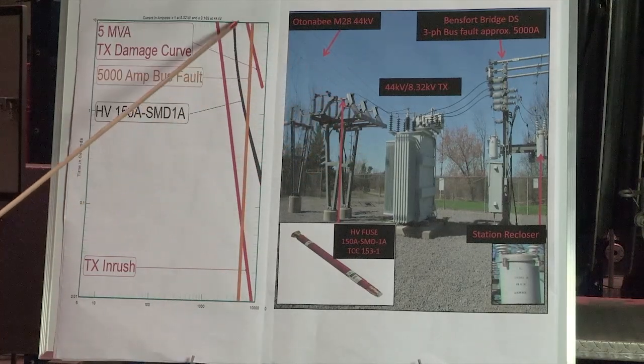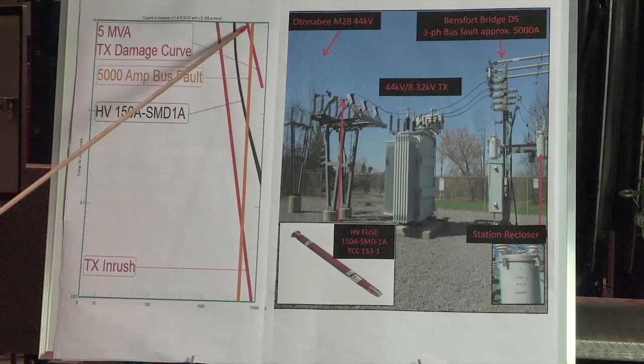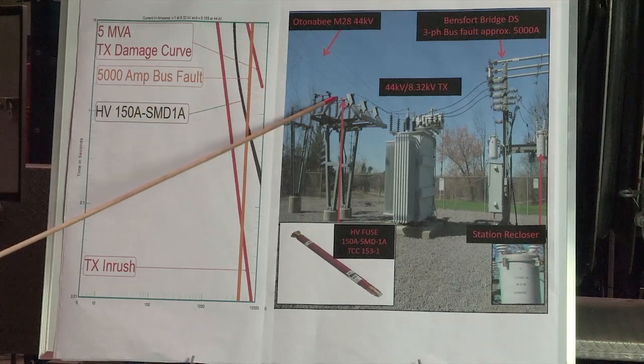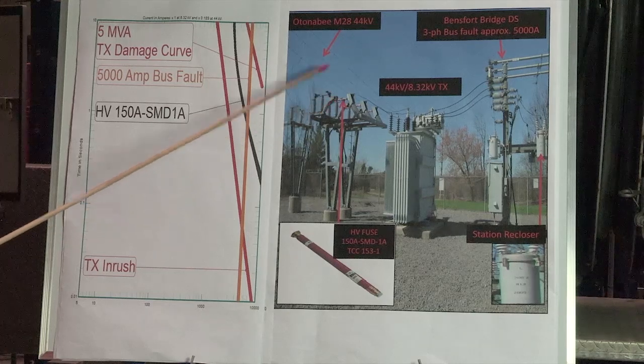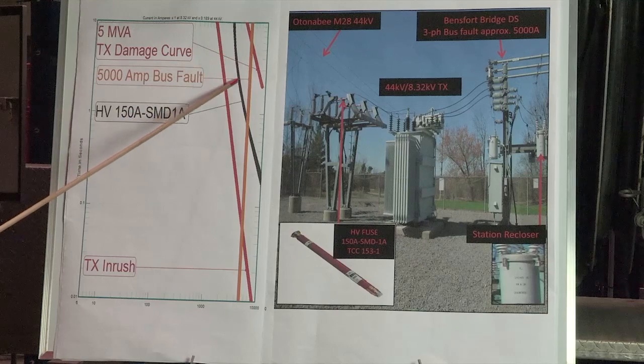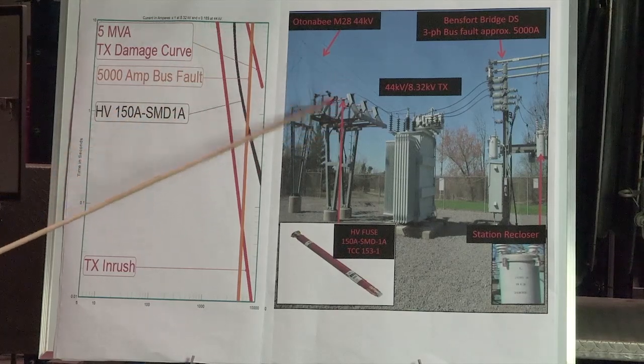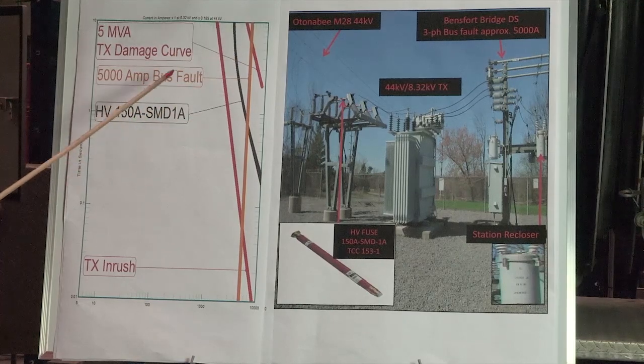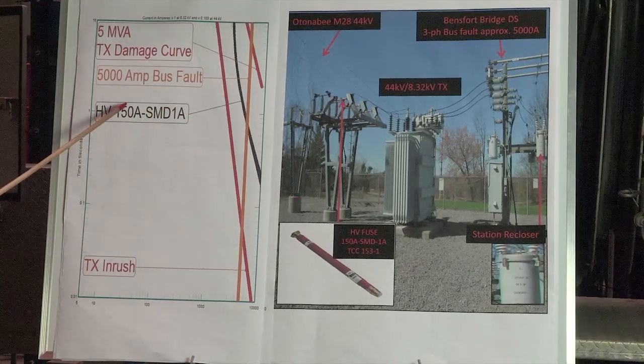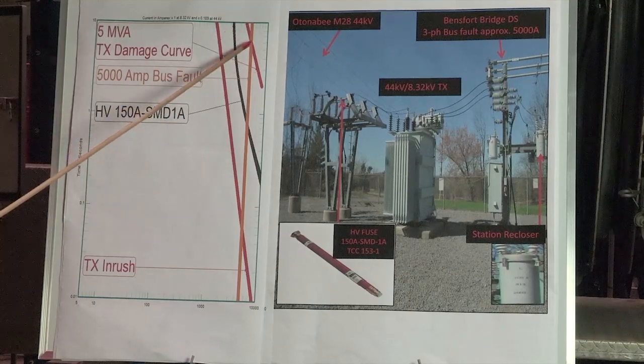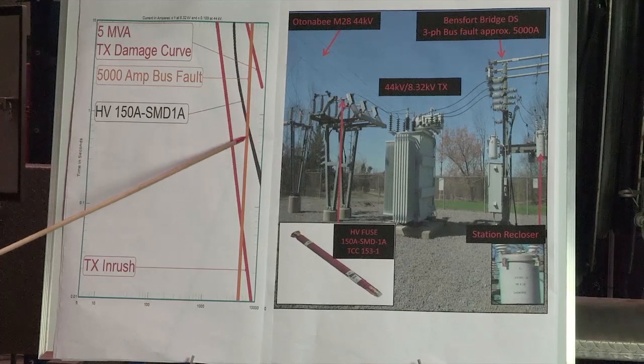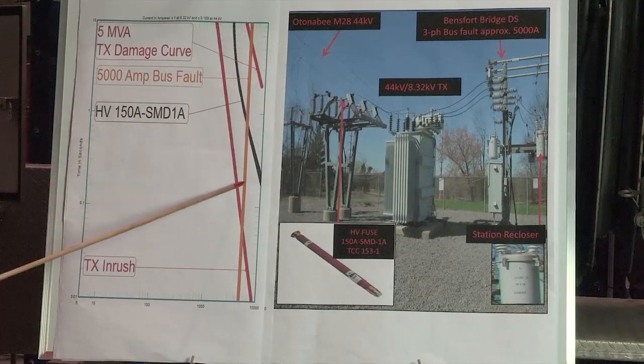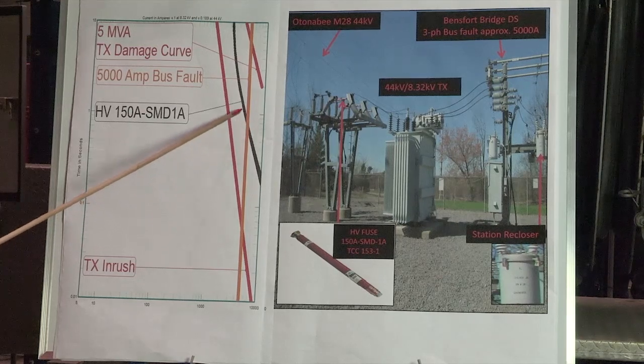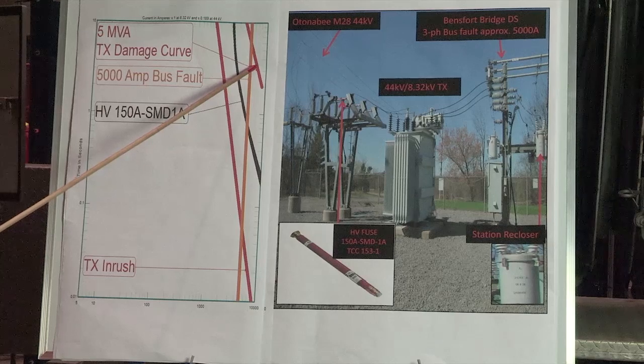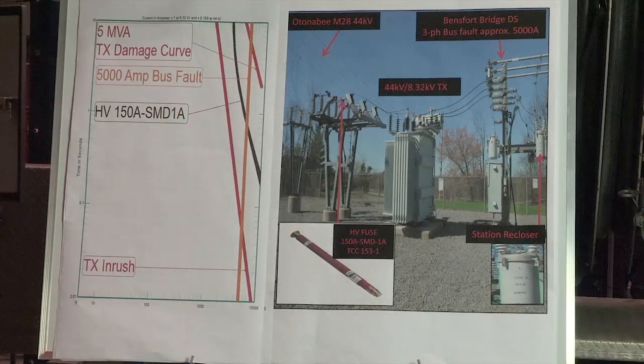So now that we have our transformer damage curve in, we are able to see from our GIS models that there's approximately 5,000 fault amps at this DS bus. So within these fault amps, we're going to have to distinguish what size of high side fusing, which is this line right here, this curve, in order to protect this transformer. So in this case, we're going to be using a 150 amp SMD1A standard type fuse that's going to protect this transformer from a fault of 5,000 amps. If there is a fault of 5,000 amps, this orange line is showing that this fuse will pop before the transformer damage occurs, clearing the fault and not having a transformer blow up.